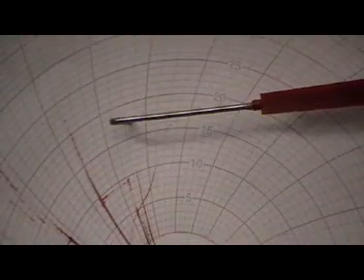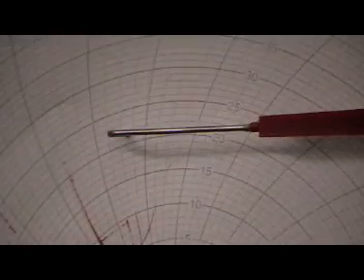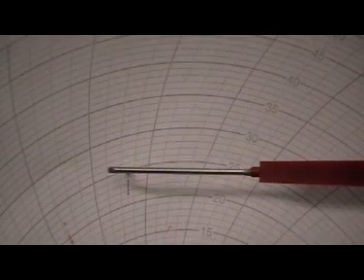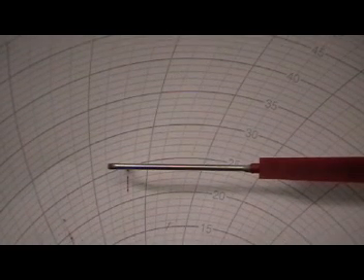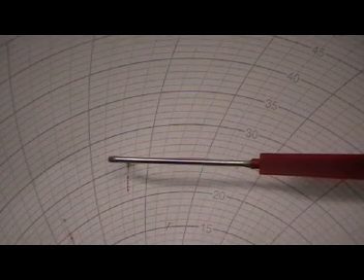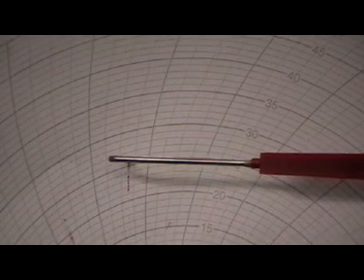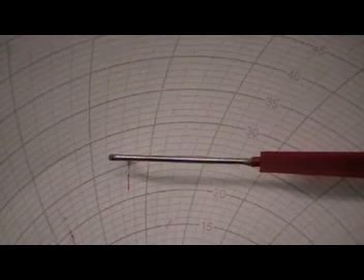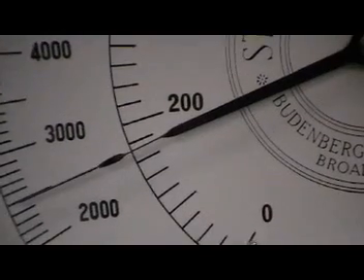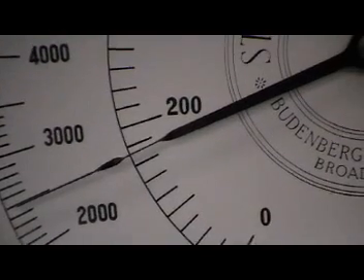As I said in the start of the video, this has been delinearized. So, we go to halfway up the chart. There were 2500 on the test gauge and we're actually reading 2600. This has been deliberately delinearized.